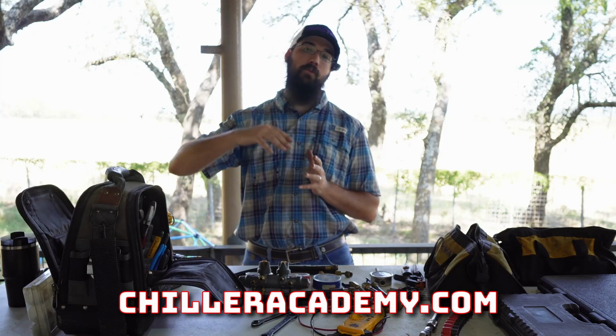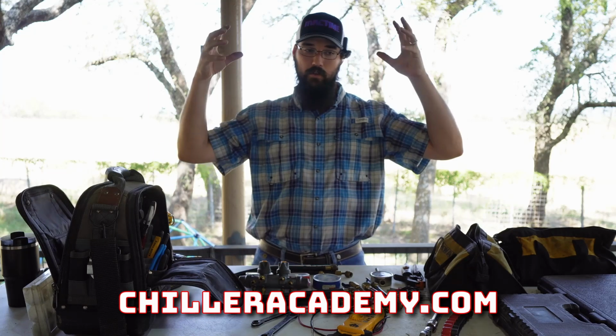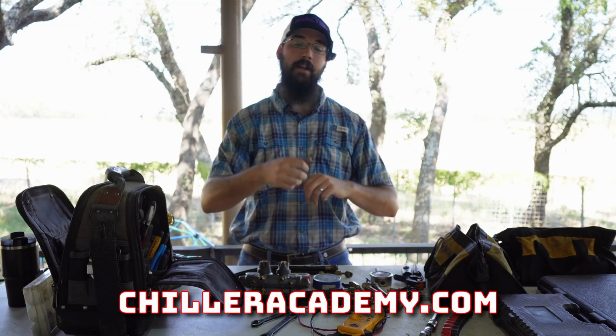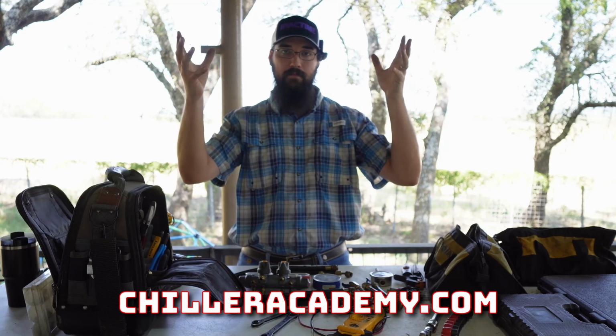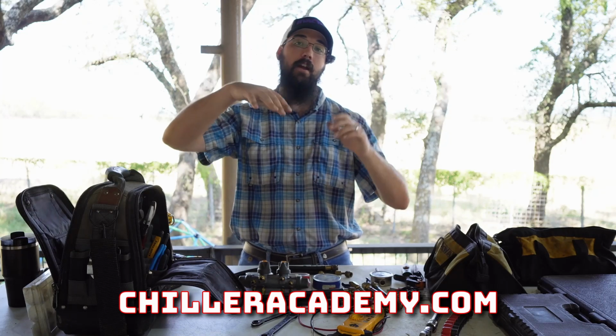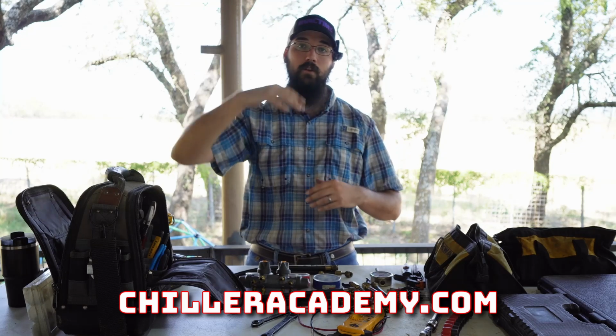Okay, so if you go with a 240 pound cylinder and above, you're going to need a hanging scale. And so that's quite literally a scale you'll set up on a set of gantries. You'll need a chain fall and rigging, and then you'll just calibrate everything with it hooked up in the tank sitting on the ground, and then you just have to chain fall that tank up in the air. And then that scale will monitor your tank weight as you go.